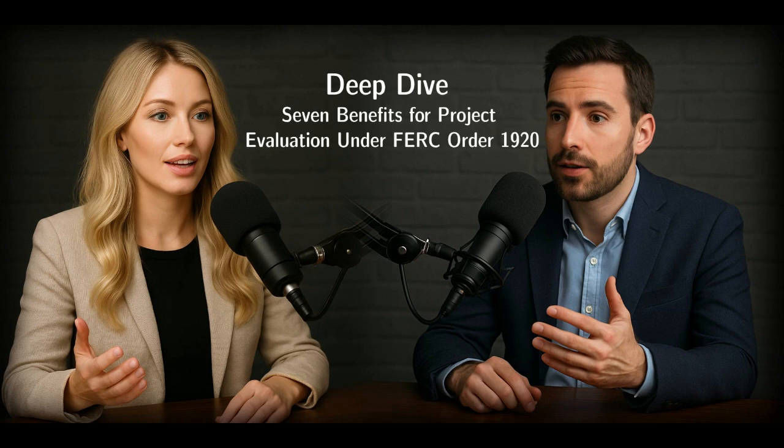This uses the value of lost load, or VOLL. And think about this. For residential customers, VOLL might be, say, $3 to $15 per kilowatt hour, depending on how long the power's out. But for commercial, it jumps to maybe $15 to $50 per kilowatt hour. Industrial could be up to $500 per kilowatt hour. And then you get to data centers, where every second of downtime costs potentially millions. That VOLL can be a staggering $1,000 to $10,000 per kilowatt hour. That's the real cost of unreliability laid bare. That puts it in perspective.